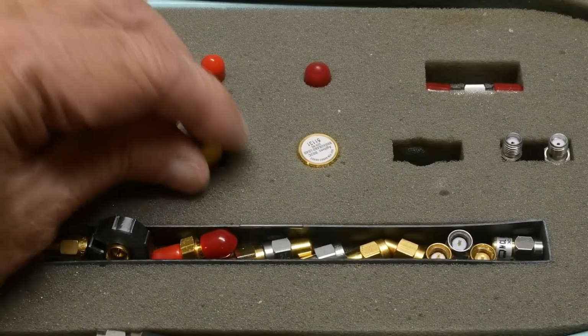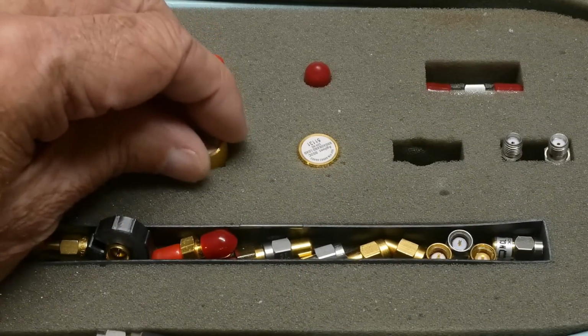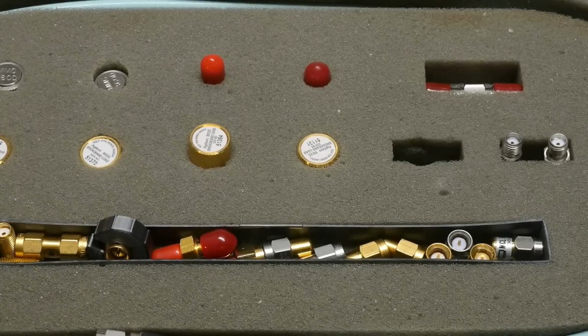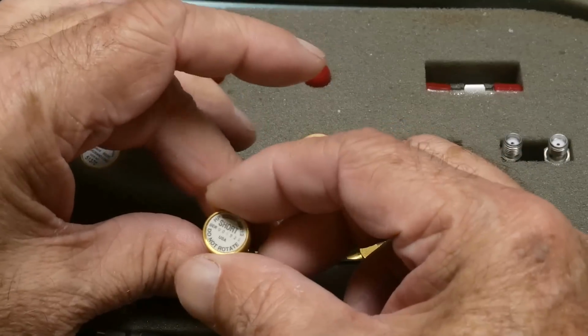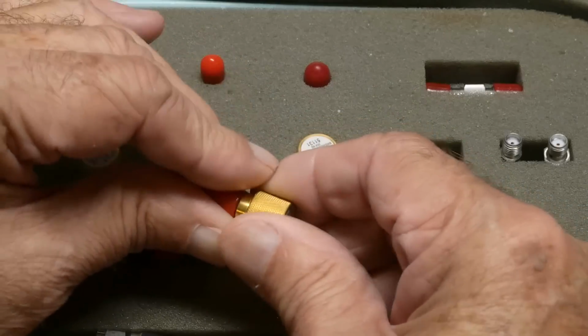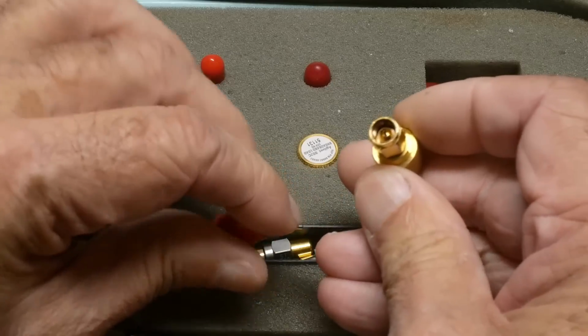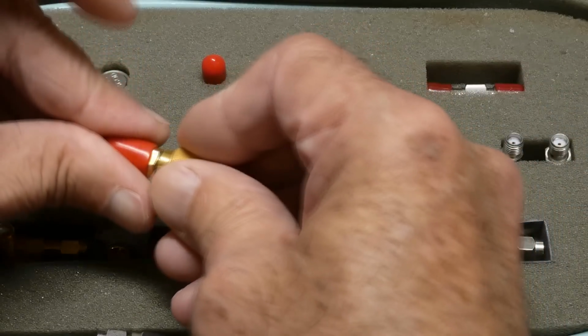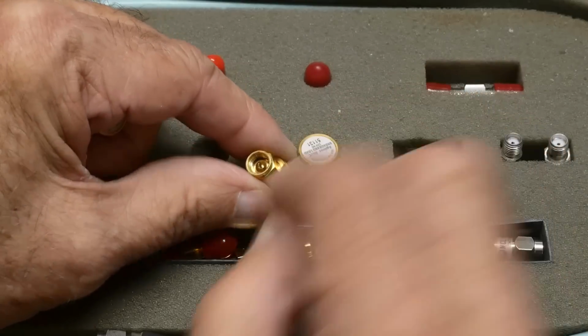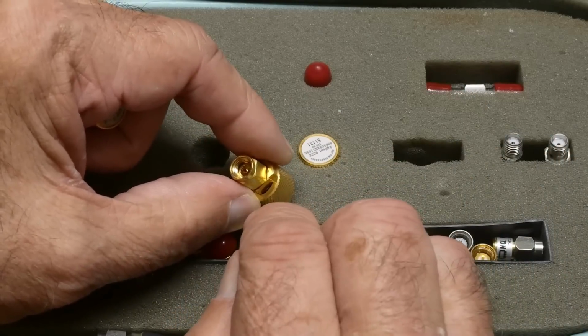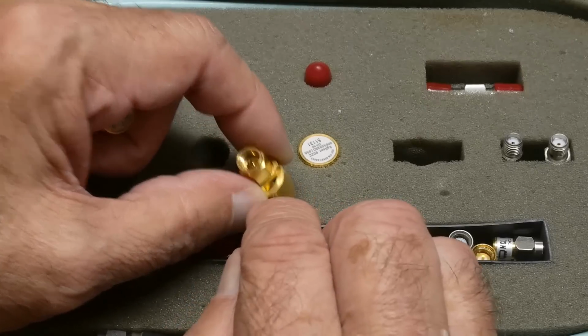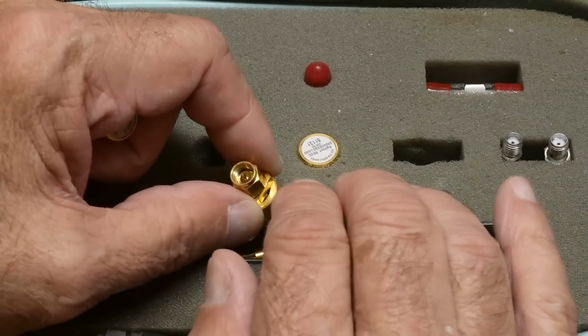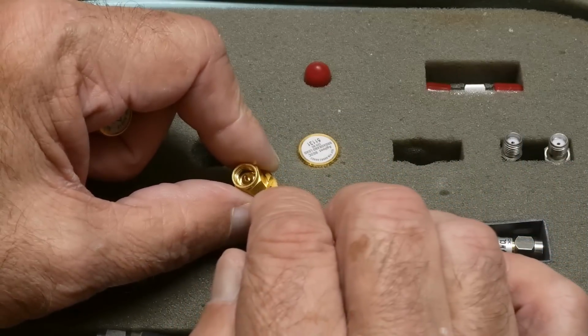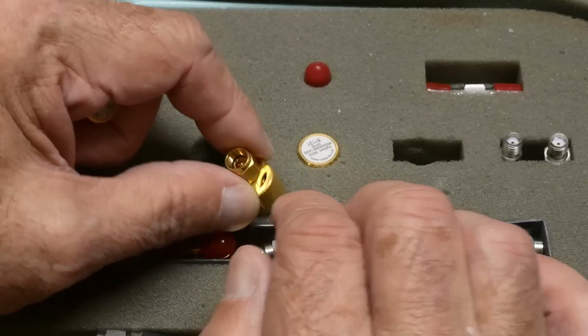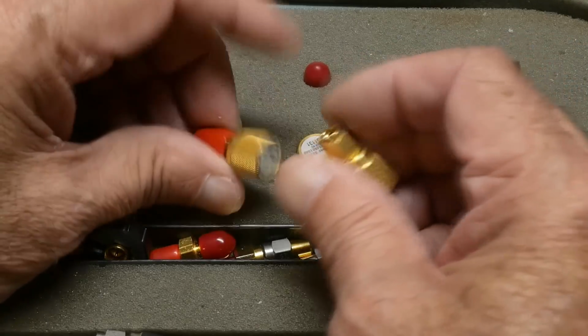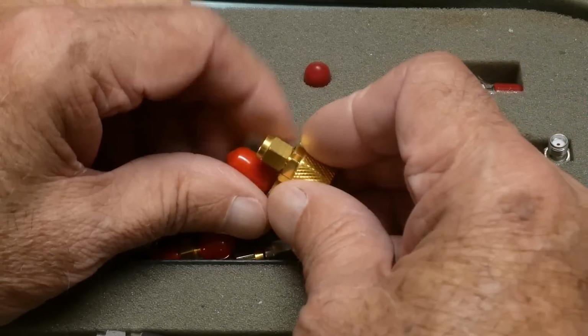the box. When I received the box, there was no male short, so I had to purchase one. I wanted one to match, and so I spent $75 buying a short. So I'll show you these up close. The load is 3.5 millimeters, and so there's a center pin, there's an air dielectric, and then there's a reference plane. So that reference plane is exactly on the surface there. And then the actual load itself is kind of deep, like maybe 2 or 3 millimeters deeper into the connector, okay? And so if you have a short, it needs to be exactly the same distance in as well.